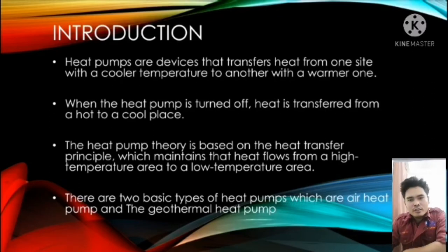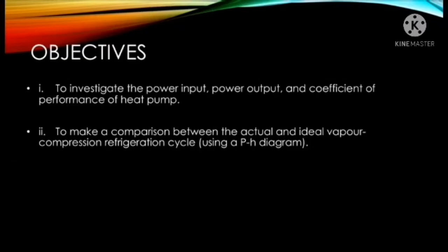And for the geothermal heat pump, a horizontal collector loop is positioned at a depth of nearly 1 meter below ground level, which absorbs the stored solar energy from just under the ground surface. This is an effective way for a wider land plot, with the exact area required depending on the heat pump capacity and the thermal conductivity of the soil in a specific location.